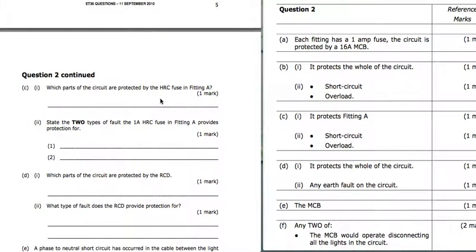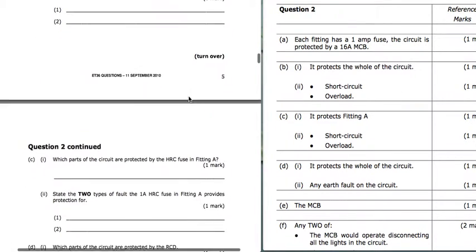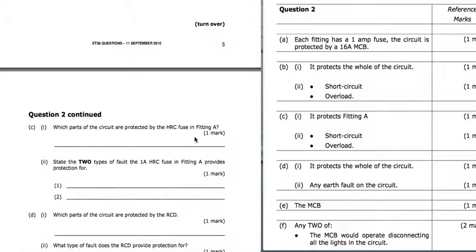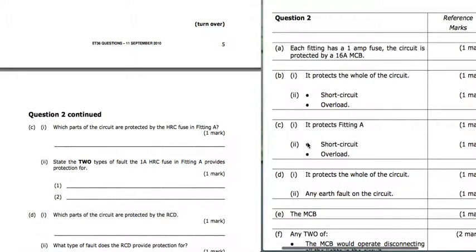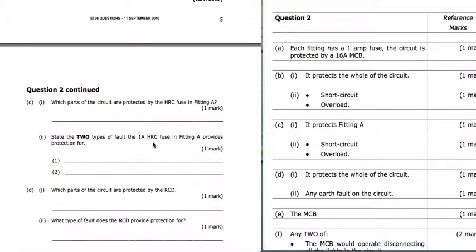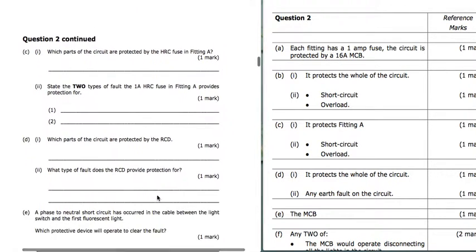Which parts of the circuit are protected by the HRC fuse in fitting A? And that answer is, it protects fitting A. State 2 types of fault the 1 amp HRC fuse in fitting A provides protection for. So again, that HRC fuse can provide short circuit and overload protection. See what I mean about it? Seems too easy about what that's doing in fitting A. It's protecting that fitting. That's what they want you to be able to understand.